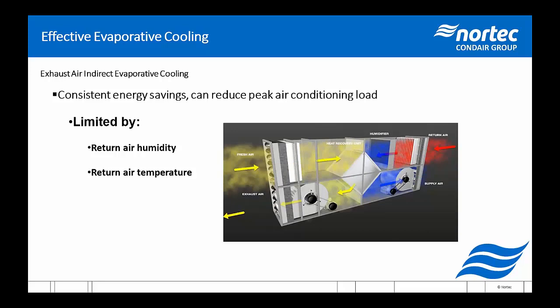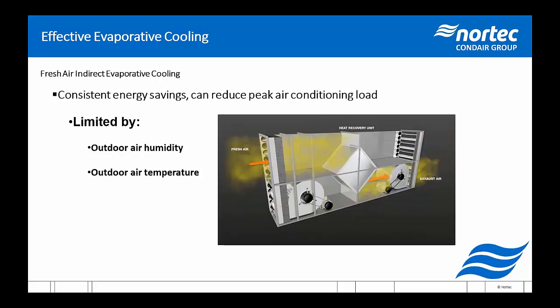We can also cool the outdoor air. So this is a 100% recirculation unit being cooled by the outdoor air through a sensible heat exchanger. If we cool that outdoor air as much as possible, again, we're seeing recovery of that cool air through the sensible heat exchanger. But we're limited by the outdoor air humidity, and we're limited by the outdoor air temperature. If the air is too cool, we can't do very much with it. And if the air is too humid, we can't humidify too far.